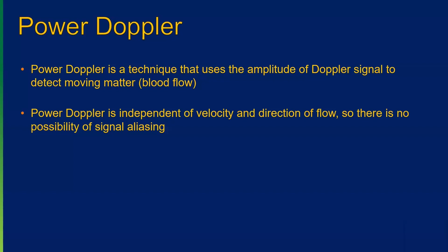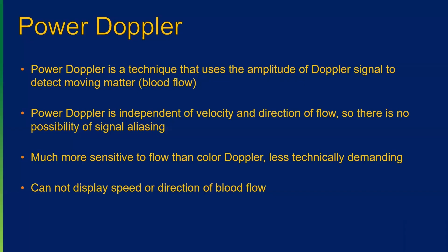Much more sensitive to flow than color Doppler and less technically demanding. We'll talk about it in a little bit, but the angle at which the Doppler signal intersects or hits a blood vessel matters. The lower the angle, if that angle gets towards zero, the better the Doppler signal is going to be. The higher that angle gets, especially if it gets over 60 degrees, the weaker and less accurate that signal is going to be. But none of that matters when we're using power Doppler. So if all I want to see is where there is flow, then power Doppler works wonderfully to be able to do that. It cannot display speed or direction of blood flow. So it just shows all blood flow in the same color scale, if you will.